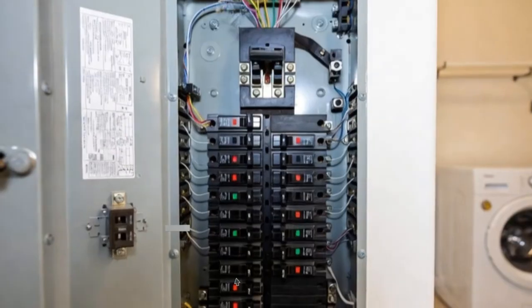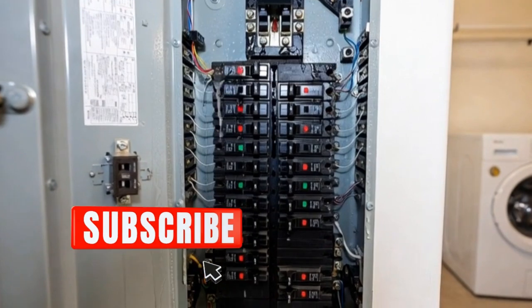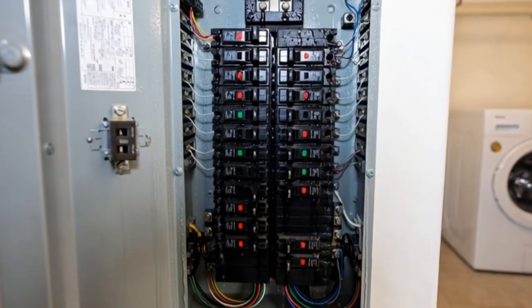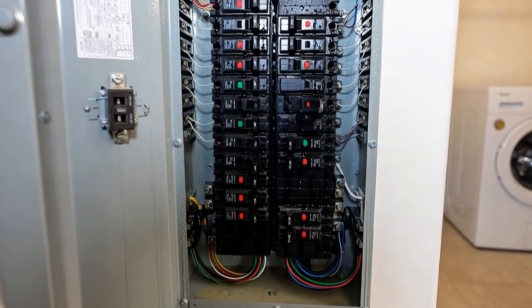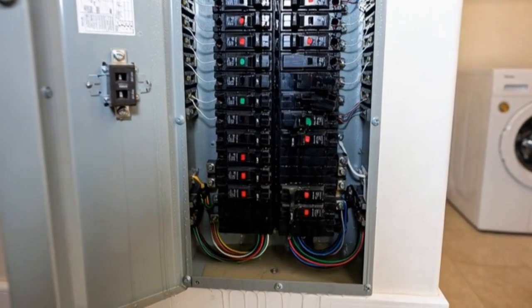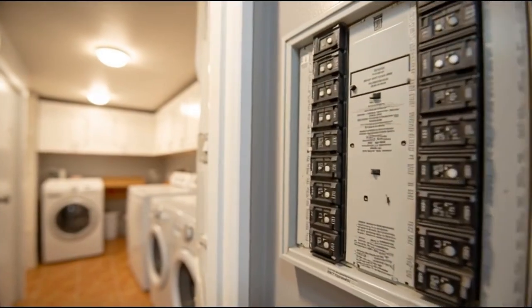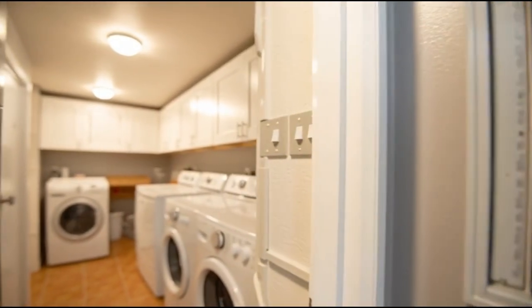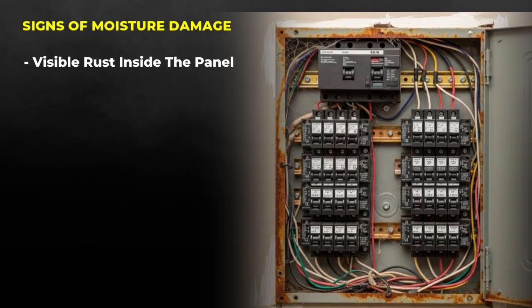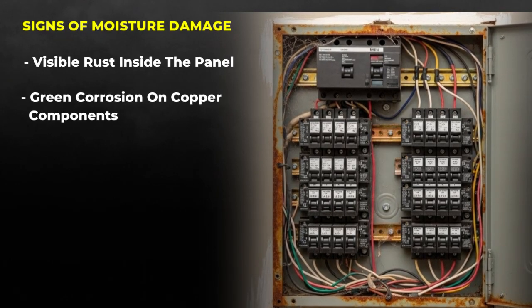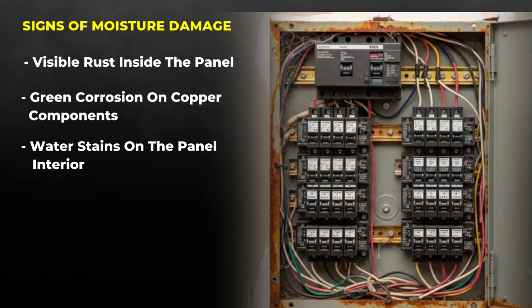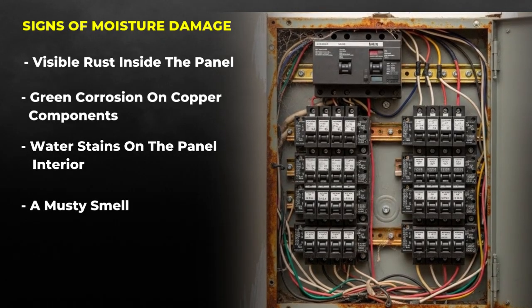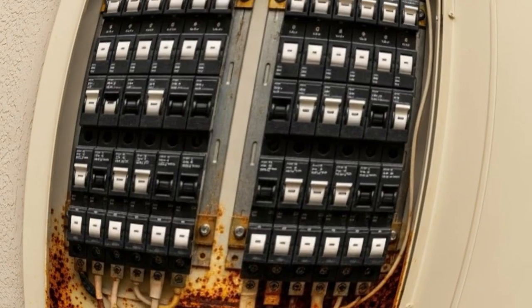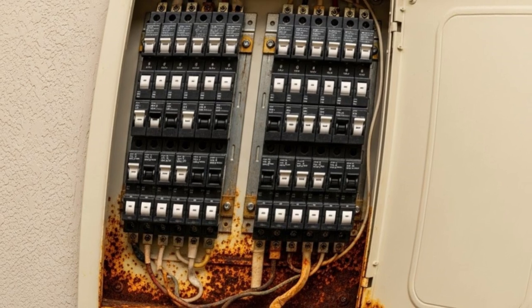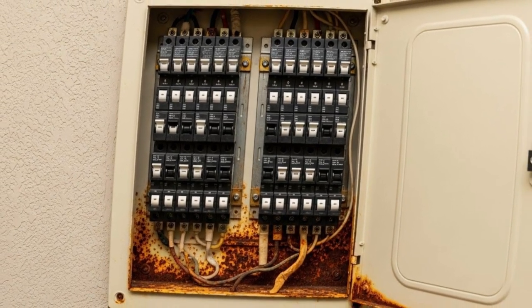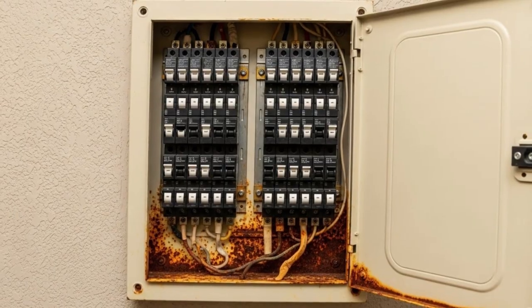Water is a conductor. When condensation forms inside a panel or water intrusion occurs, electrical current can take unintended paths. Small leakage currents flow where they shouldn't. These abnormal currents can fool the main breaker into detecting a fault condition even when no real overload exists. Signs of moisture damage include visible rust inside the panel, green corrosion on copper components, water stains on the panel interior, and a musty smell when you open the panel cover. Moisture-damaged panels are serious safety hazards. If you suspect water intrusion, do not continue resetting the breaker. Have the panel inspected and potentially replaced.